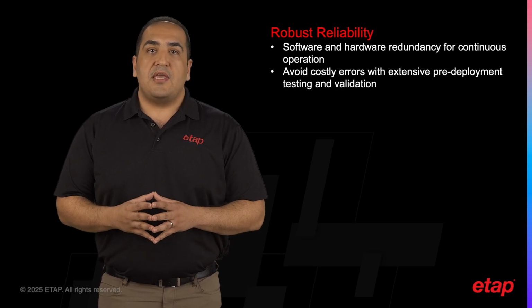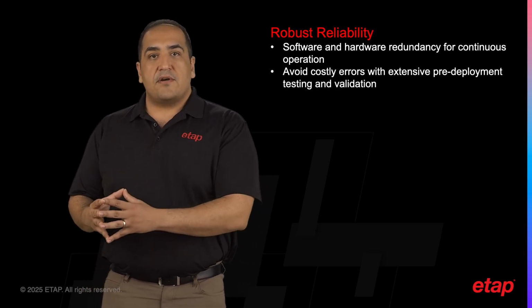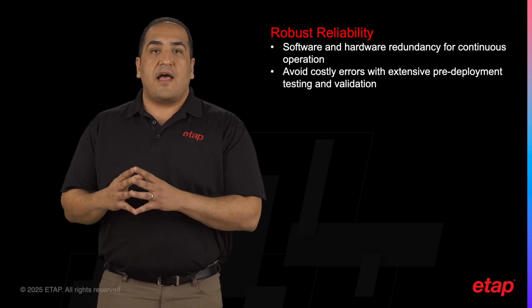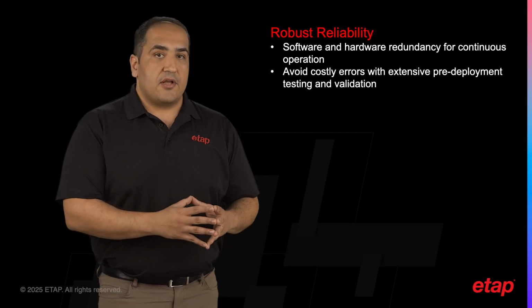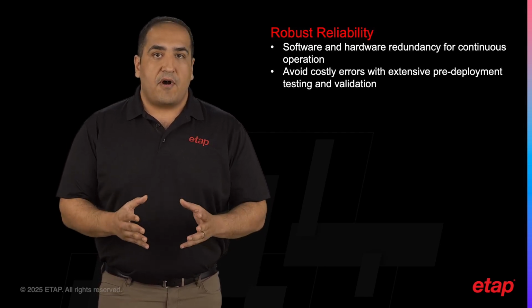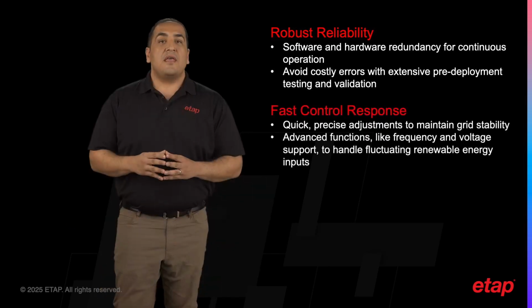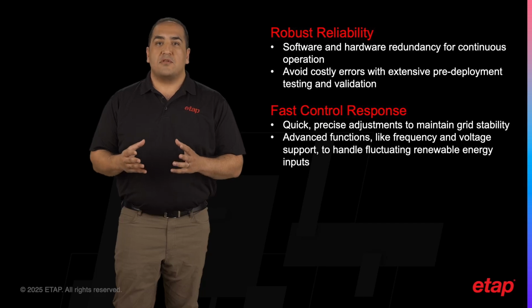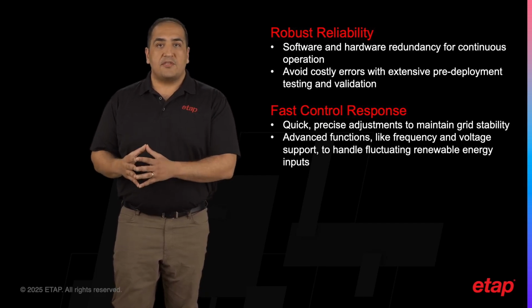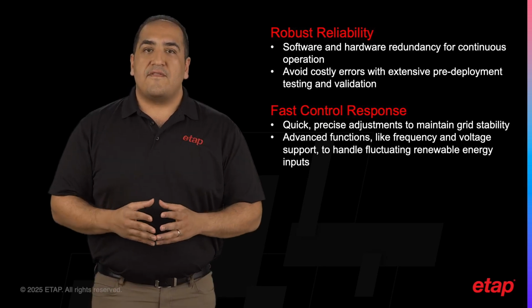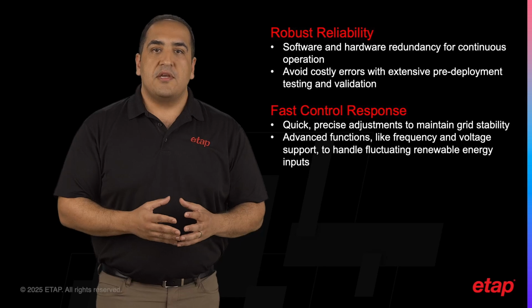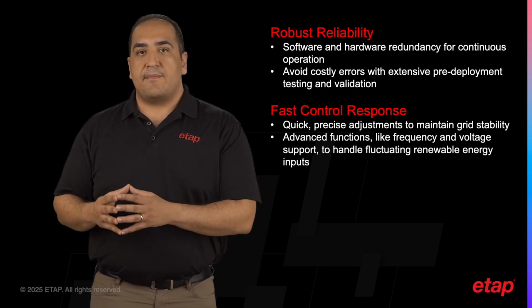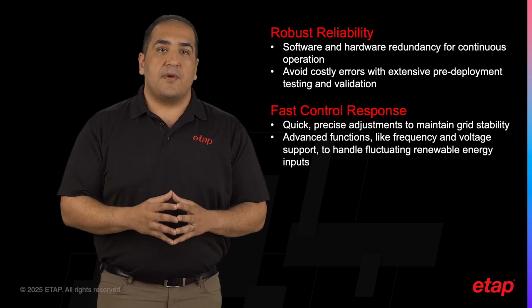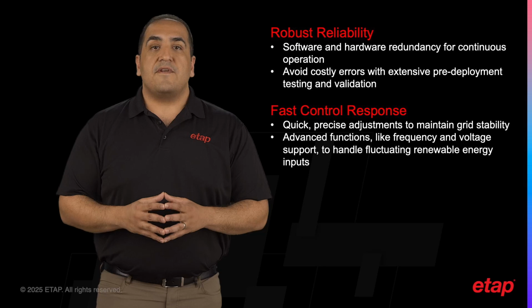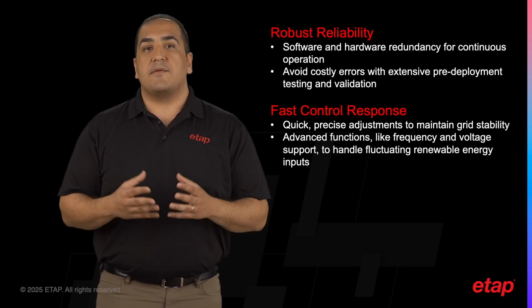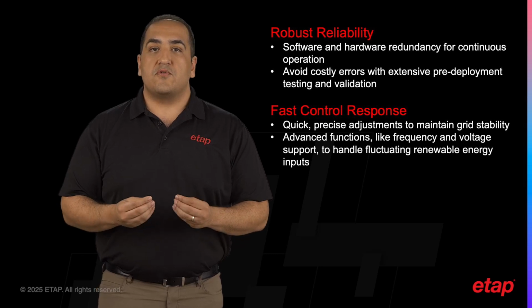Reliability is further reinforced by ePPC support for both software and hardware redundancy. This means that in the event of an unexpected failure, the system remains operational, ensuring continuous control, which is vital for power plants where downtime is not an option. ePPC also excels in providing fast control response times, enabling quick and precise adjustment to shifting grid conditions. The inclusion of advanced functions such as frequency and voltage support is particularly important for maintaining grid stability, especially in the face of fluctuating renewable energy inputs.